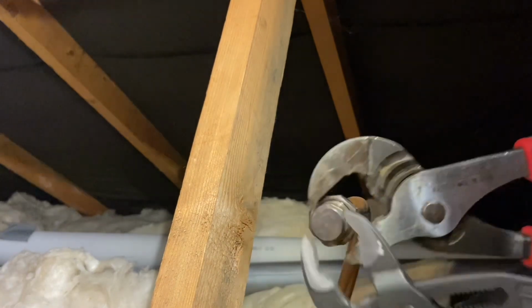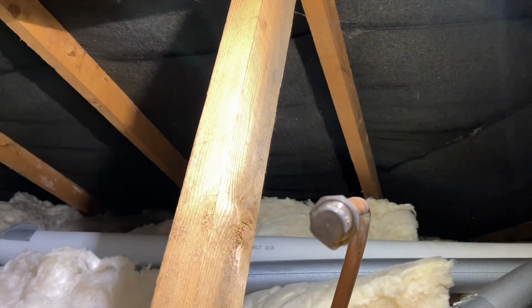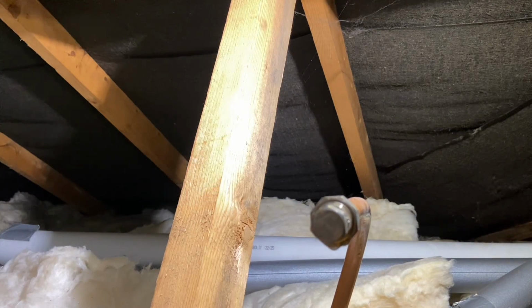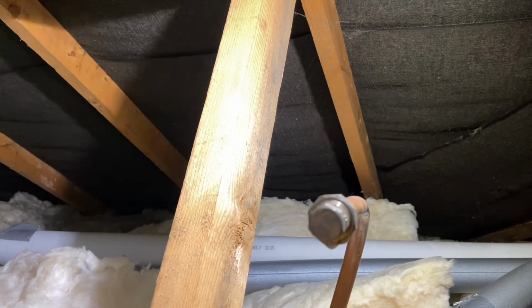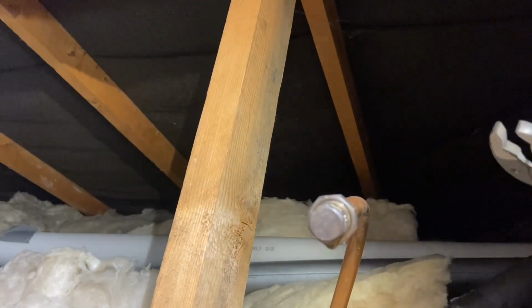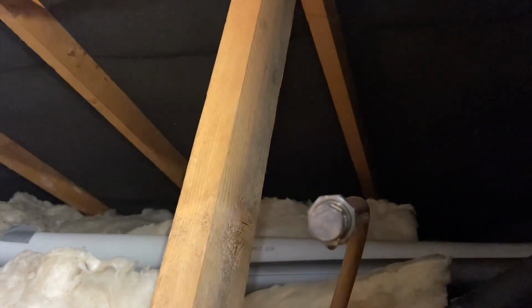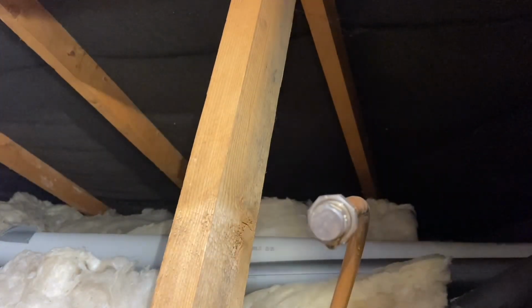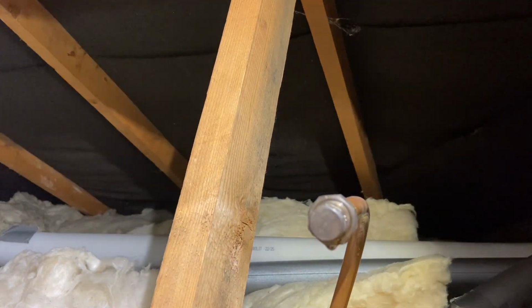Right, that's all the air out of that. Return now feels like it's getting hot. Flow's red hot. Flow down that 8mm pipe to the rad's red hot. It's suddenly gone then, hasn't it? Hopefully, yeah. Well, when we take pressure off when we're flushing, yeah. Swap it and put one of those auto air vents back on.